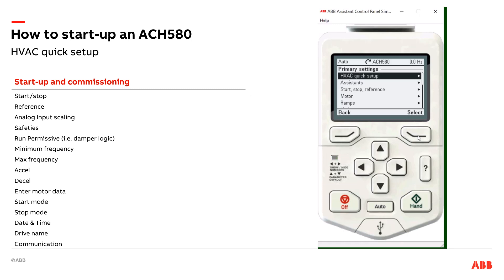I'm going to go ahead and hit select on the HVAC Quick Setup. First thing on the list is where does the drive get a start/stop signal from? Factory default is digital input one — that's the relay output from a controller coming into the drive, landing on digital input one. If I wanted to change that, say make that start/stop from BACnet, I could go ahead and edit and go into it. But I'm going to leave that at start/stop on digital input one.